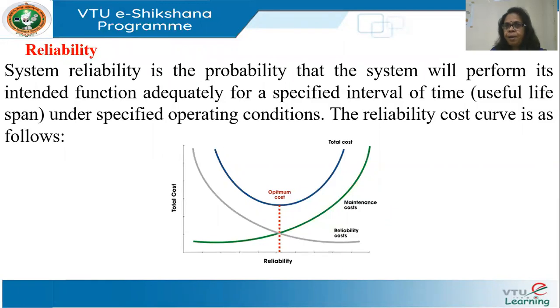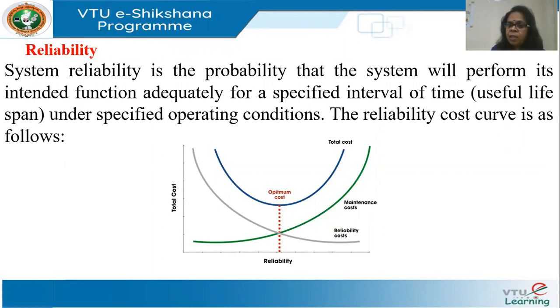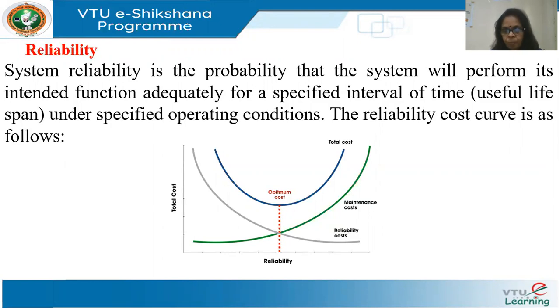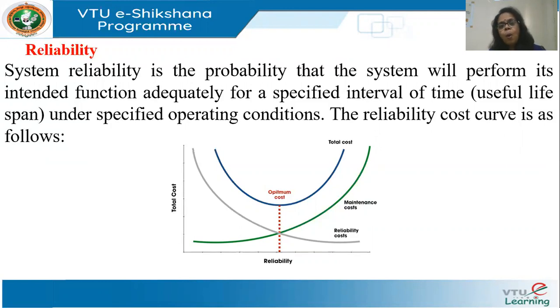If I have all lines without any parallel lines, and one line gets outaged, there will immediately be an overloading condition. Without redundancy, the reliability of the system is definitely reduced. So I have to build redundancy and control equipment that I may or may not use. Building reliability costs money. The cost is of two types: how much money you spend to make the system reliable, and what is the cost you pay if you don't make the system reliable — for example, loss of load or investment in a new generator.